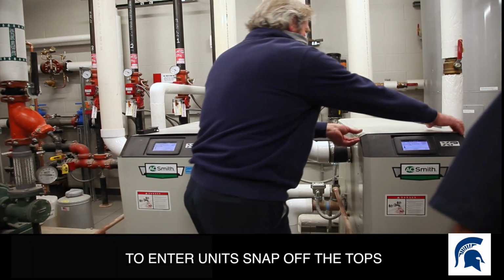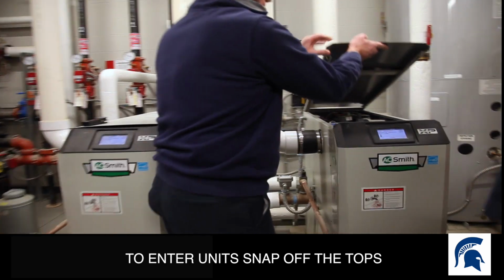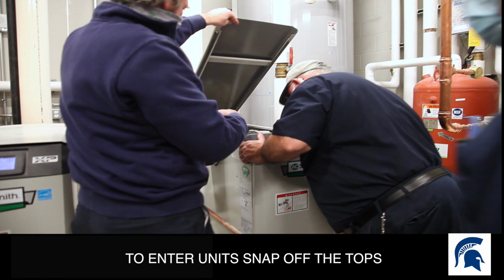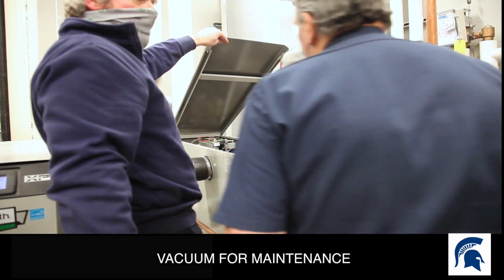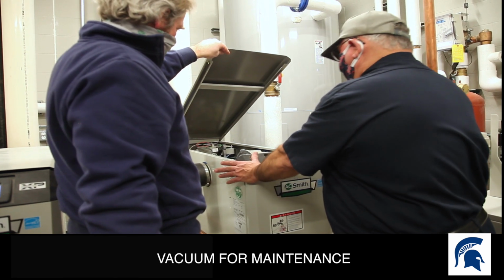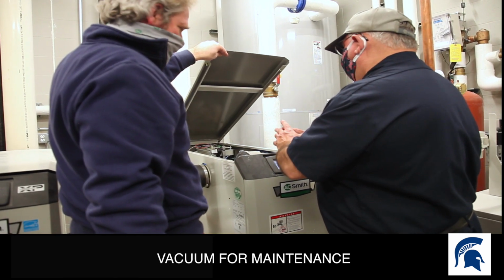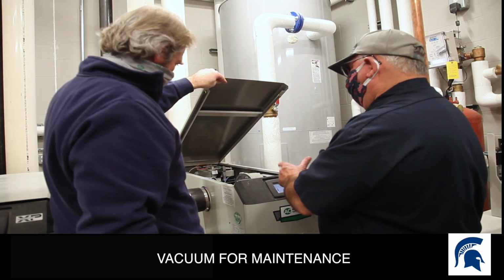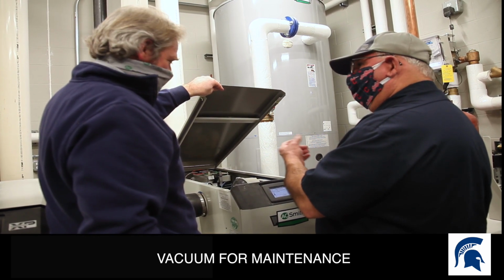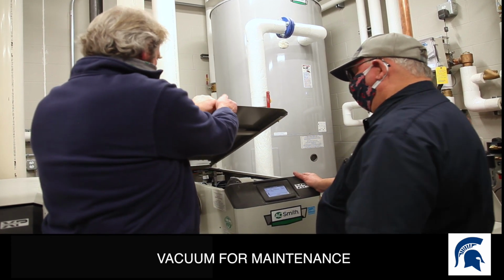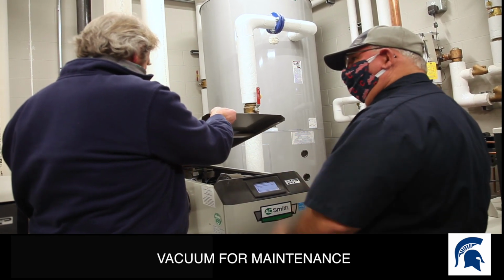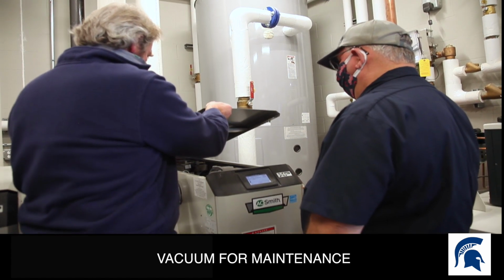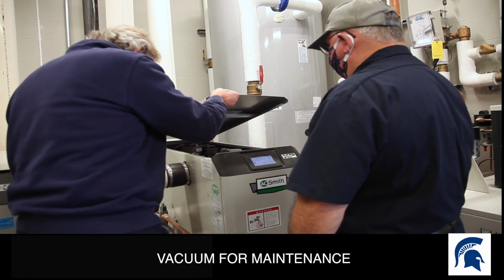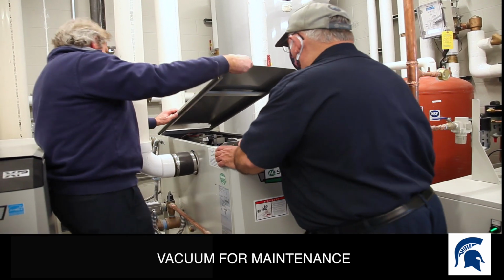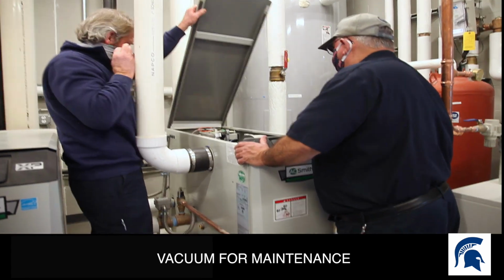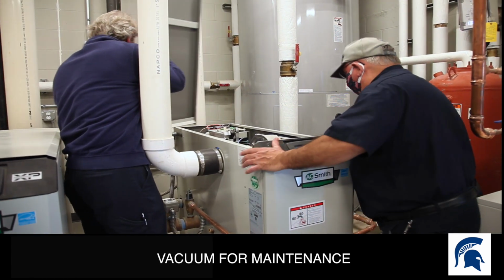And to get into these units, they're just snap-ins, snap off like that. You can see in there. Vacuum in here, guys, clean that out a little bit. Keep it clean in there. Okay, when you're in here, is there any filter or any kind of firing plug? It's all electric? There's no spark igniter. No, you don't have to clean. The igniters that are in there, if they go bad, you'll have to change them. Does that come off on a heater, or just the whole thing comes off? No, the whole thing comes off.